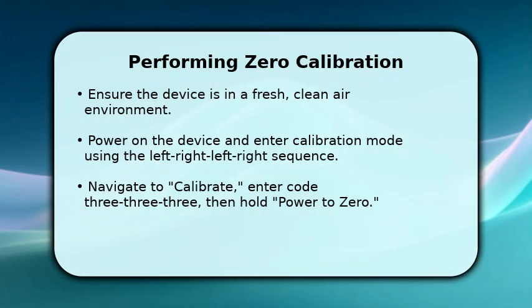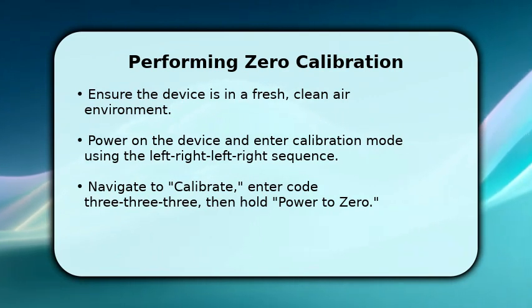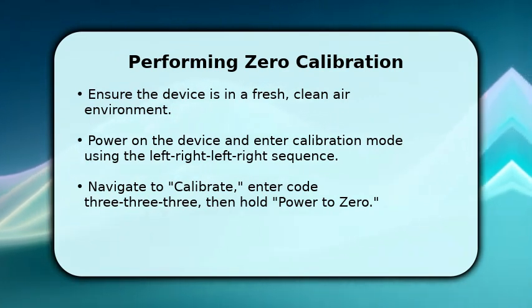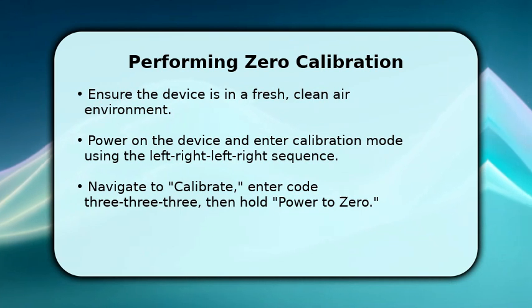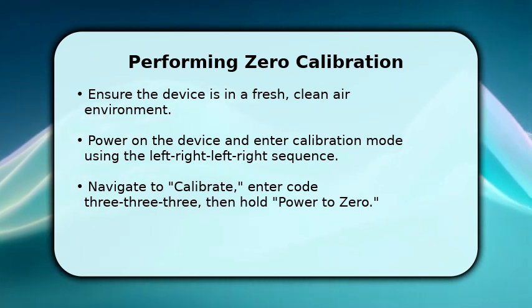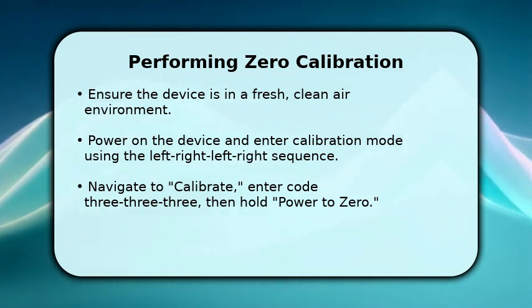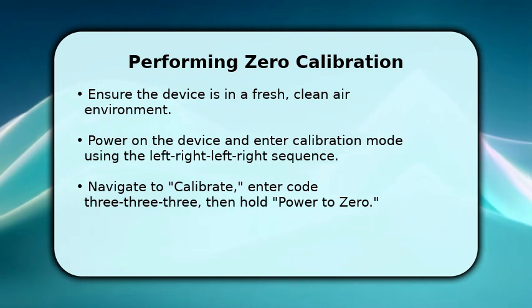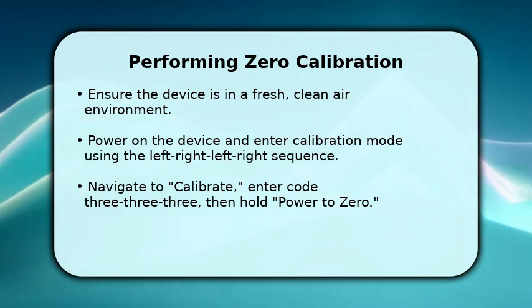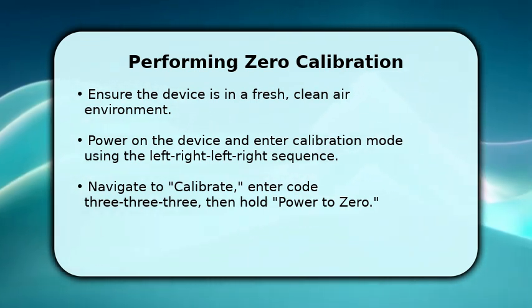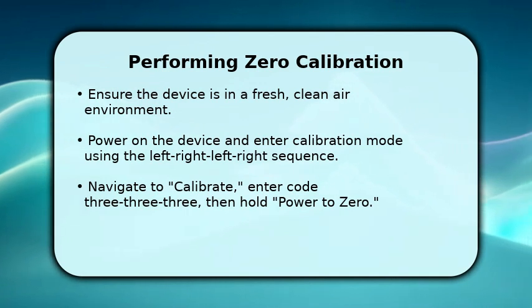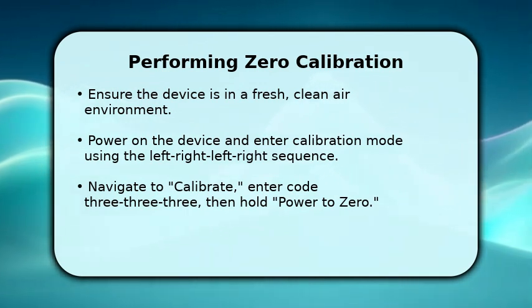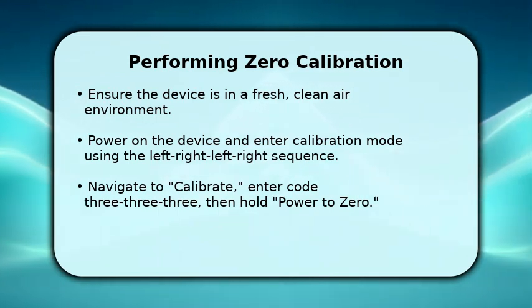Let's begin with zero calibration. First, ensure your GMI PS200 is in a fresh, clean air environment, free from any gas contaminants. Power on the device, and as the countdown starts, immediately press the left, right, left, right buttons to enter calibration mode. Once in the menu, navigate to Calibrate, enter the code 333, and then hold the power button to zero all sensor ranges. Release the button once zeroing is complete.